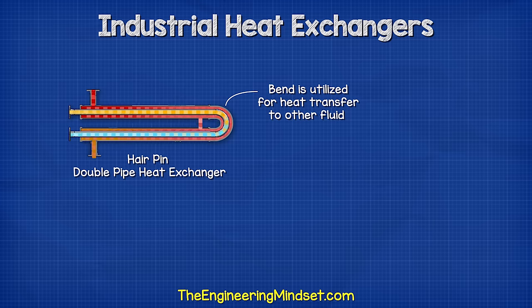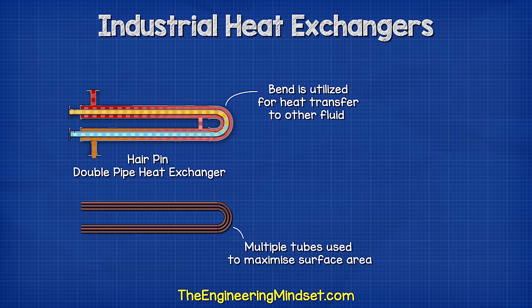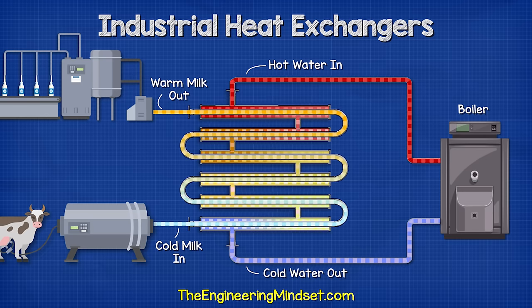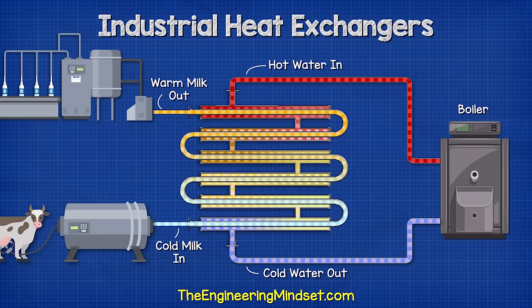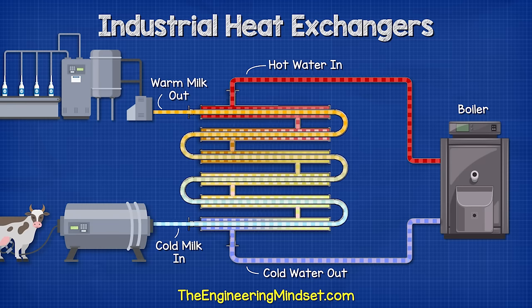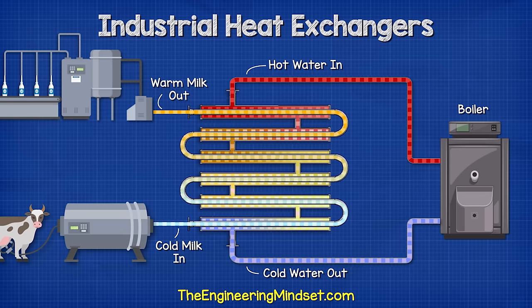Other designs, like the hairpin type heat exchanger often found in oil refineries, encapsulate the bend to fully utilise the surface area for heat transfer. This version normally uses multiple tubes to maximise surface area and increase heat transfer, although it also increases resistance. These are a fairly simple design and very common in food processing as well as pharmaceutical production. For example, a dairy product might flow through the tube, while hot water or steam flows in the opposite direction through the shell, warming the product to a certain temperature before it is mixed with other ingredients and bottled.